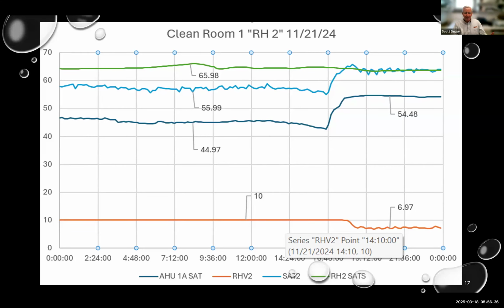You look over the time that you've got the trend available over a cold day, and you look at valve position and the set point you're trying to reach. And here, what you see is the valve was fully open, but it wasn't meeting set point because it had to lift the temperature of the supply air coming into the coil from 44 up to 65, and it couldn't do it. So we need a bigger coil here. So this one is a fail. I think that's the slide you wanted, right?